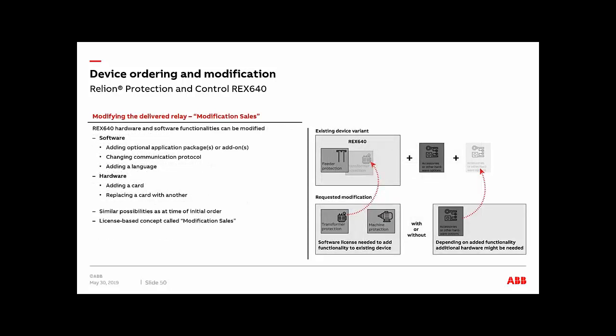Even after you have ordered, you have your relay with you. So pretty much you will get something when it comes to software. You can have your additional package or an add-on if needed. You can change your communication protocol. You can add a new language. And if required, you can add a new I/O card. Or if you have a package that requires an extra analog, if you had the 2-winding, now you want a 3-winding package, you might need an extra set of current. So you will be required to have the software and the hardware as well.